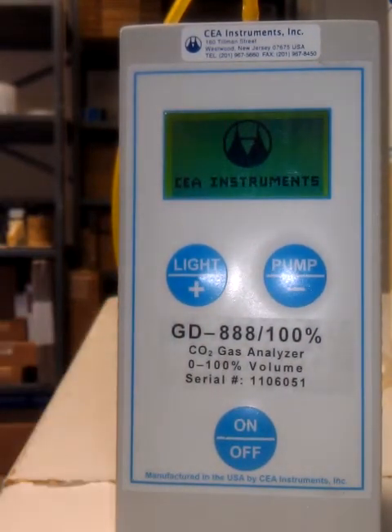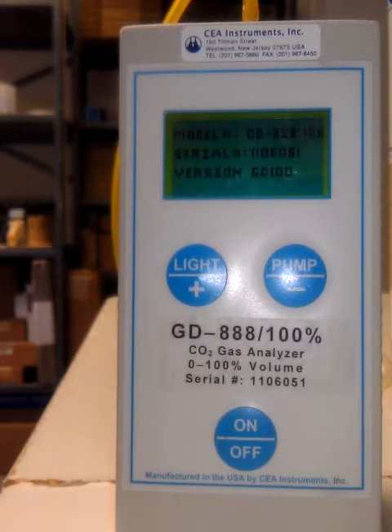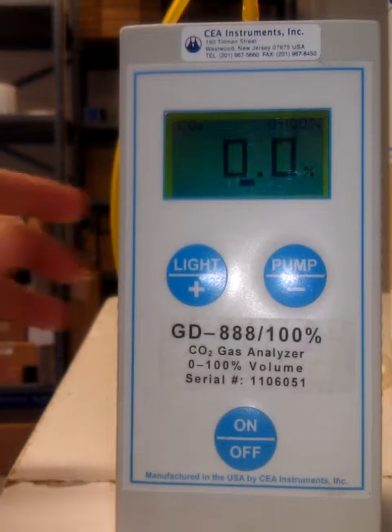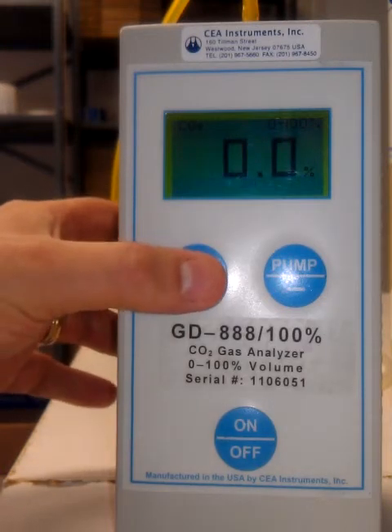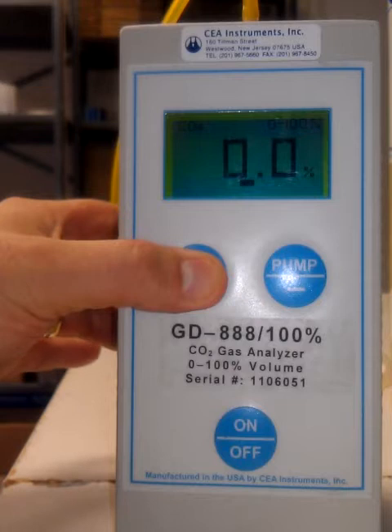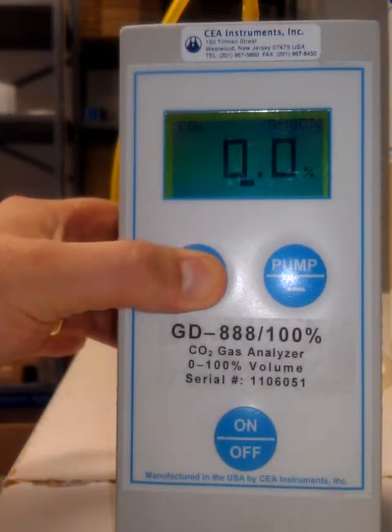When you first turn on the unit, it tells you it's CEA Instruments, the version, the serial number, and the range. GD-888-100, serial number, and it's the GD-100 version. Shows you the gas. You can turn the light on and off by pushing and holding. Every time it beeps, the light is turning on and off.